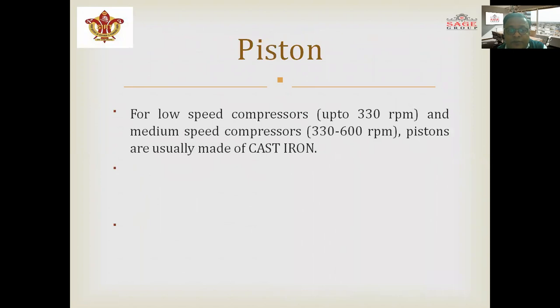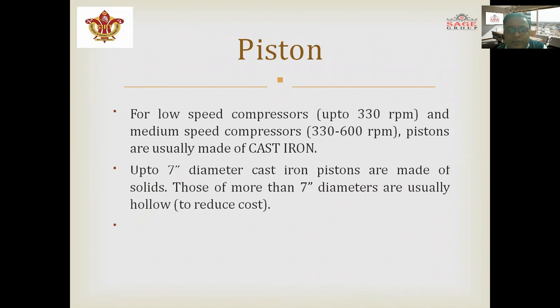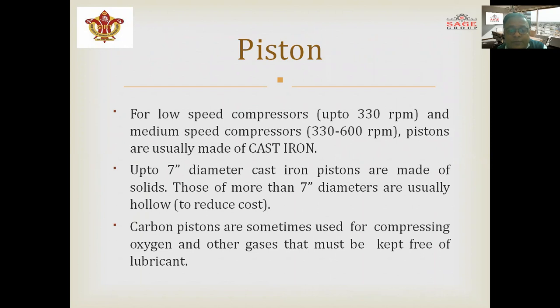For low-speed compressors up to 330 RPM and medium-speed compressors from 330 to 600 RPM, pistons are usually made of cast iron up to seven inches in diameter. Carbon pistons are sometimes used for compressing oxygen and other gases that must be free of lubricant.